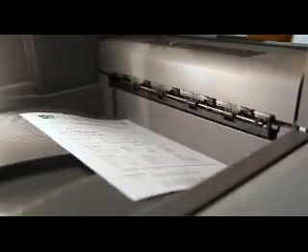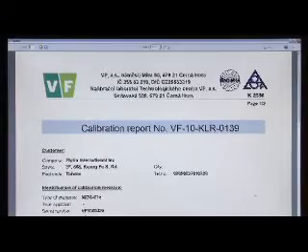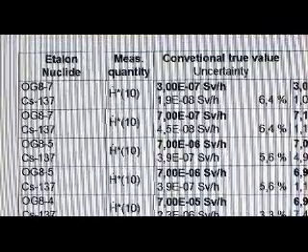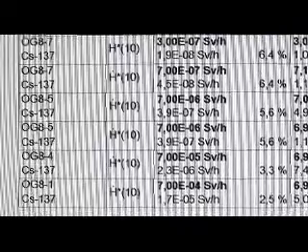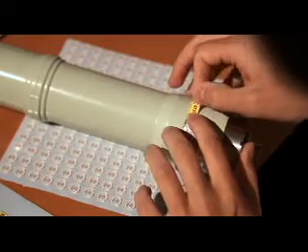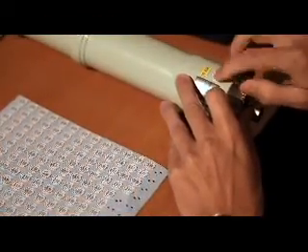The control software automatically creates a calibration report using the values measured and stored in the database. The software also provides overviews and analysis of the measurement results, together with other data stored in the database, without the necessity for any physical paperwork. Subject to successful calibration, the instrument is labelled with a sticker which shows that it conforms to national standards. The process is completed by the issue of an official calibration report.